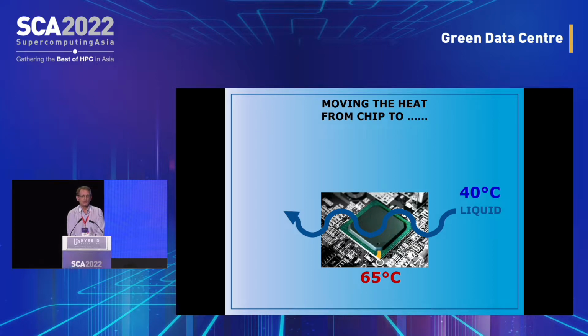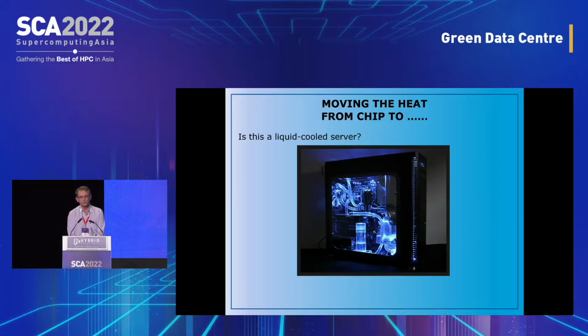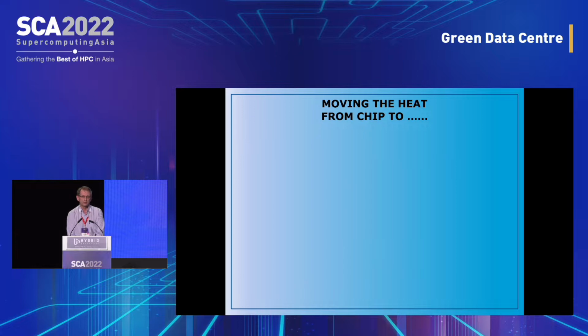And we're moving the heat from the chip to, what are we moving it to? Here's an example, is this a liquid-cooled server? It's got liquid pipes running around inside it, so it looks good. But actually no, this is not what we mean by liquid cooling, because this equipment still requires an airflow through it to take away the heat. So this is not what we really mean by a liquid-cooled server.